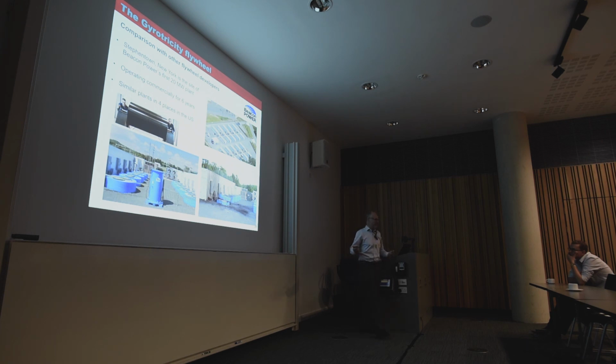And I'm sure they had an investigation and looked at it. This other one was a steel flywheel that went off. It was just huge. What happened there is the bearings went. It wasn't properly bolted down. It went round. It was in a bunker, and it went into the ground, blew soil into the building, and took the roof off. This is a huge flywheel. I just wouldn't do that. There are reasons for doing that, but I don't think it's worth it.